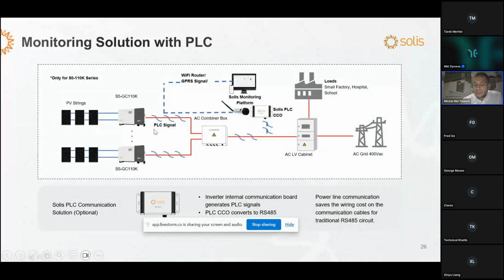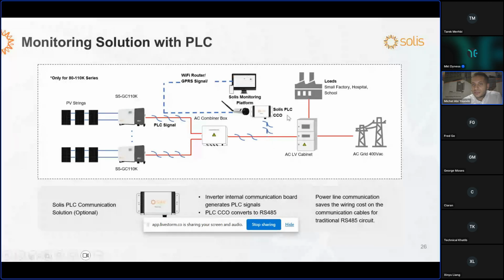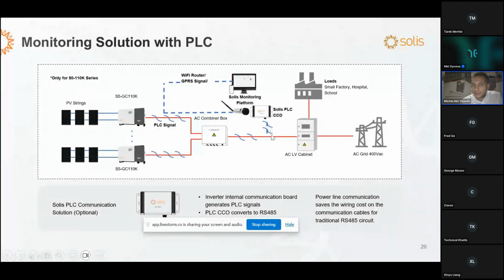If on the field and on the inverter, the internet is not available, we can use our power line communication solution for monitoring. So the inverter will send the signals to power line communication on the AC cables, and our solution will collect the information from the power line and send it to the cloud. So here in this solution, it is not necessary that the inverters are connected through RS485 or through data cable.